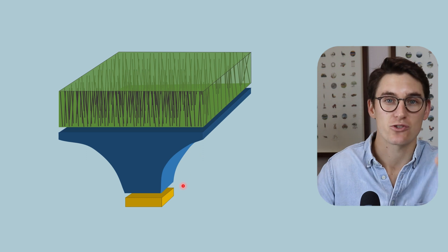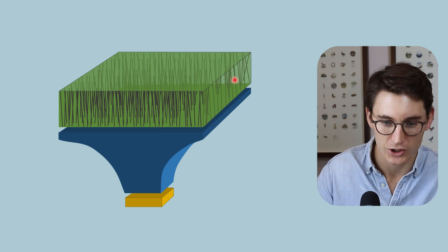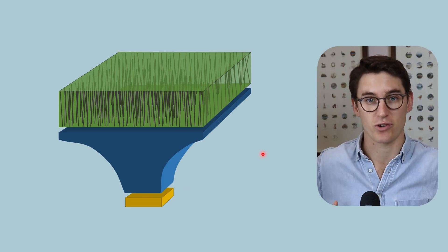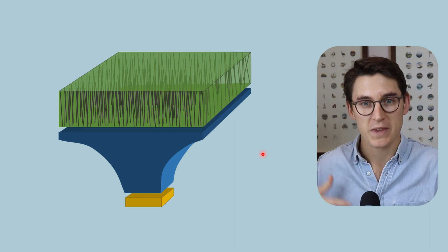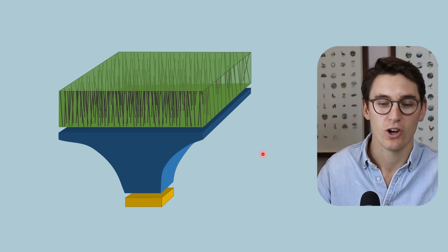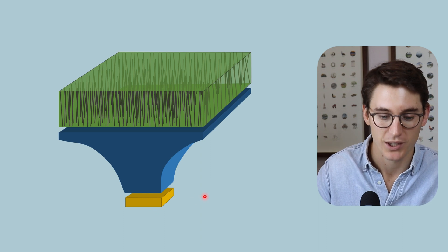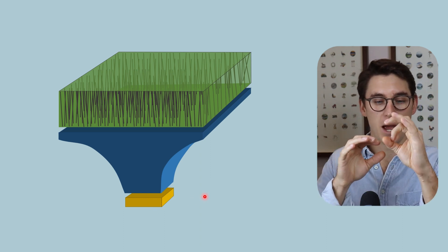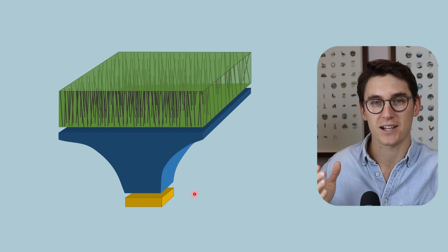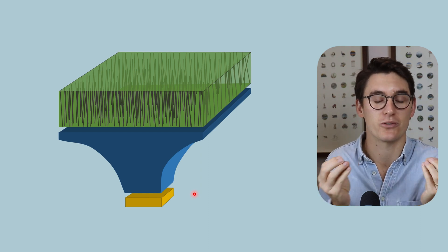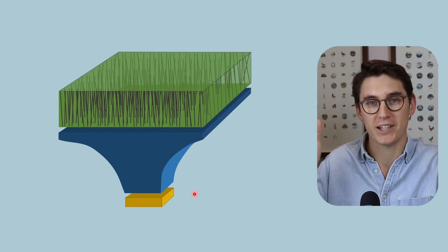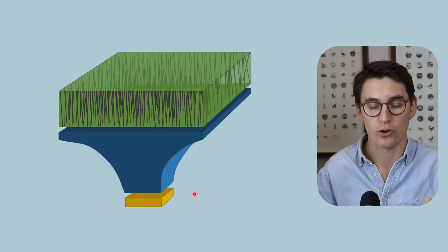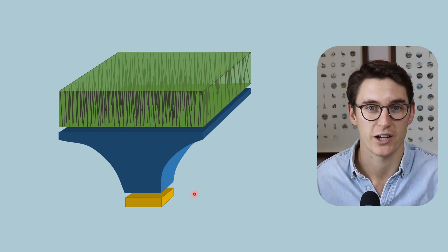Now the second reason we get drop-off is because we've got a really large area here. If we're taking an X-ray of a large body region and we need to focus that down onto a very small chip. These chips are small enough to fit in the camera. They are tiny and we are focusing that light down and there's always going to be a loss of some resolution whenever we need to take such a large area and focus it down onto such a small area.